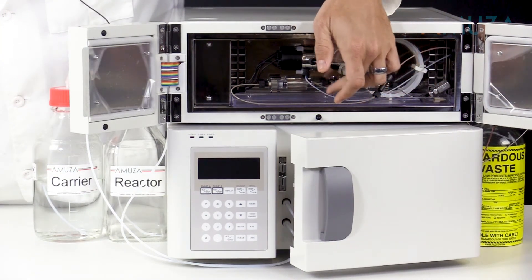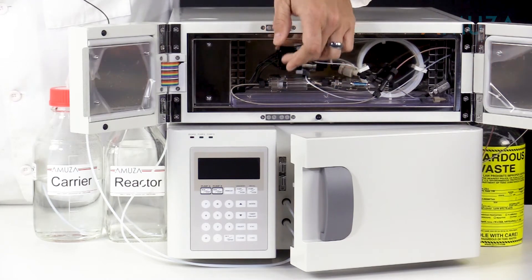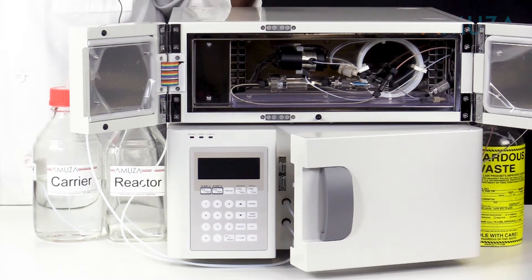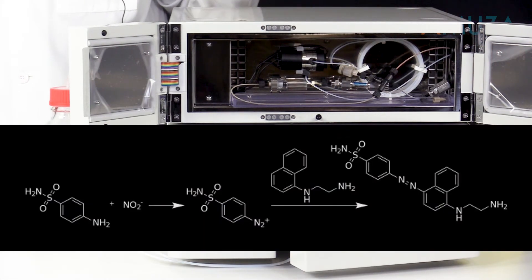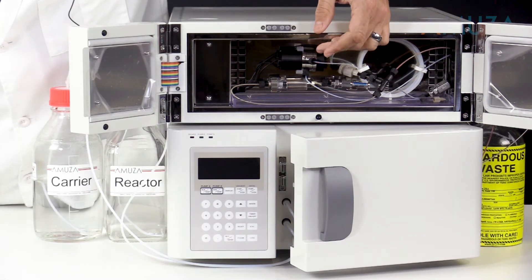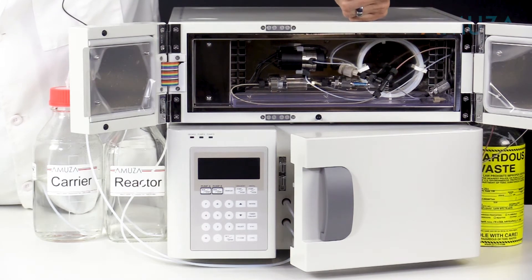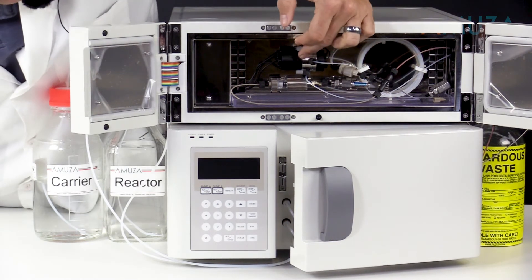After separation, nitrate is reduced to nitrite. The system utilizes the Griess reaction in which nitrite forms an azo dye and is detected as the pink color develops and is measured by absorbance detection at 540 nanometer wavelengths.